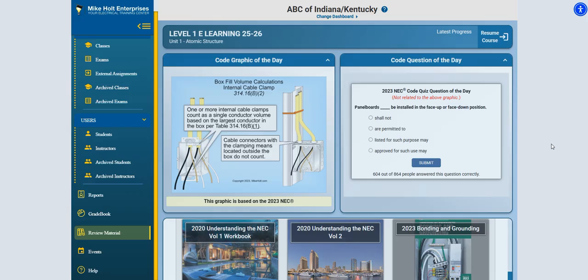Article 314.16, which if you're familiar with that article, and you should be, Article 314.16 or Table 314.16(A) is metal boxes. And that table gives you a lot of the standard metal boxes. It gives you the cubic inch space, and it'll also give you the number of conductors that can be installed in that box. That's a whole other subject for another day, but our code graphic here is indicating the internal clamp. Now, where would you see an internal clamp?